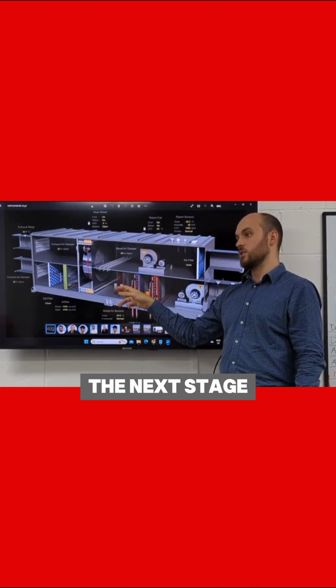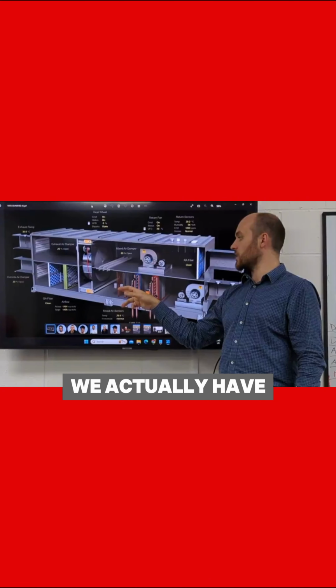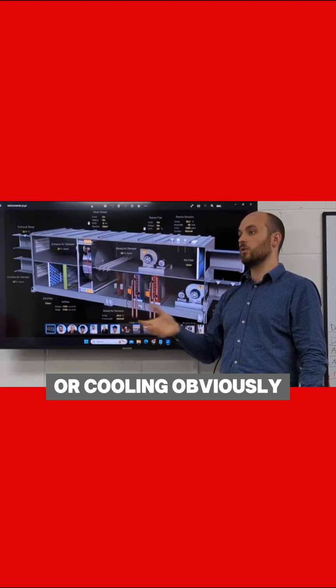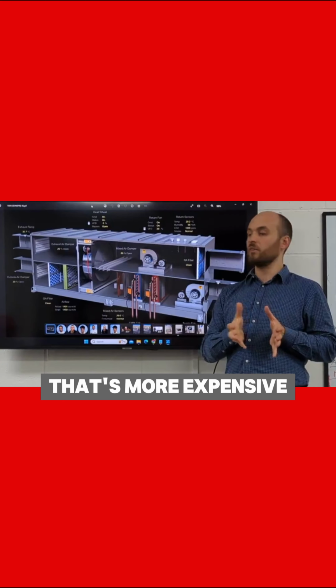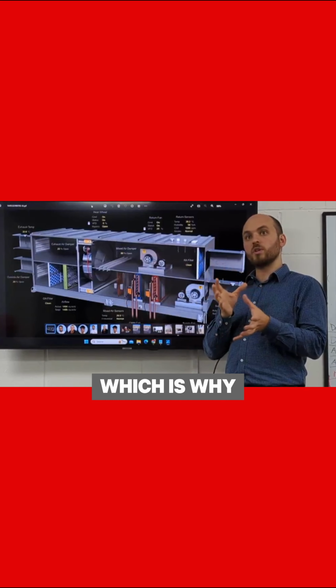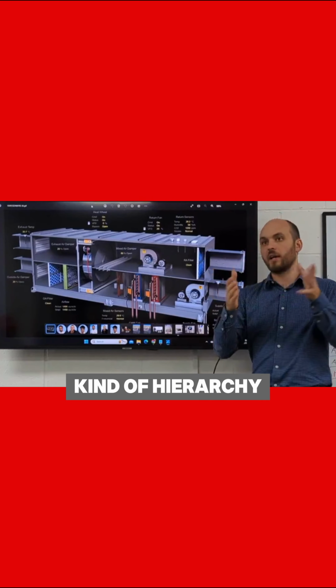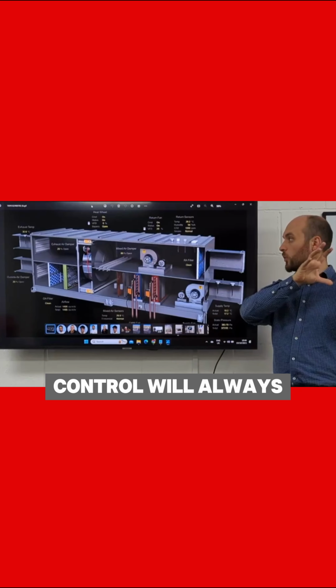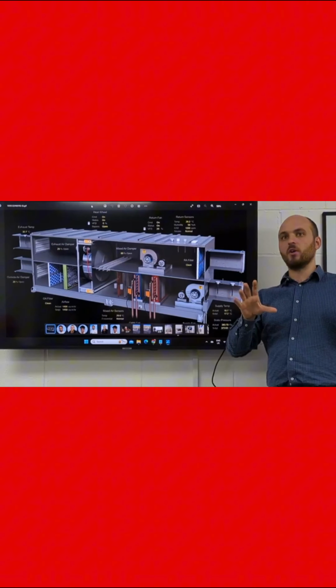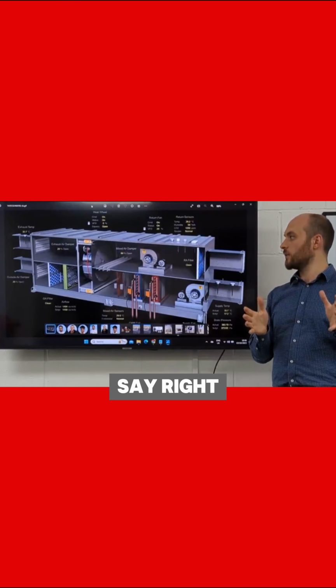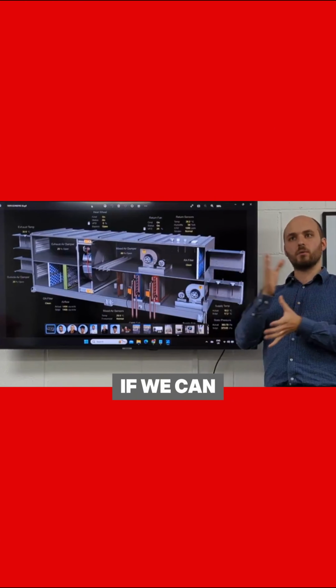The next stage of the air handling unit is where we actually have to use some form of mechanical heating or cooling. Obviously that's more expensive than turning a thermal wheel, which is why our controls will have a kind of hierarchy system. The control will always be based on saving the most energy. So the first thing we're always going to do is say, right, can we recover some heat? Great, if we can, we'll do that first.